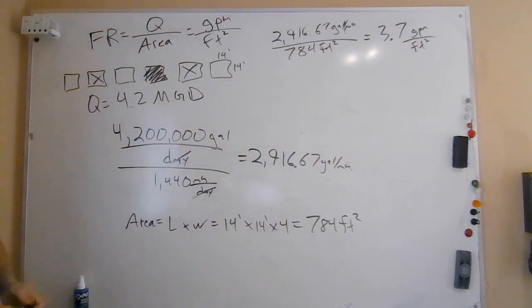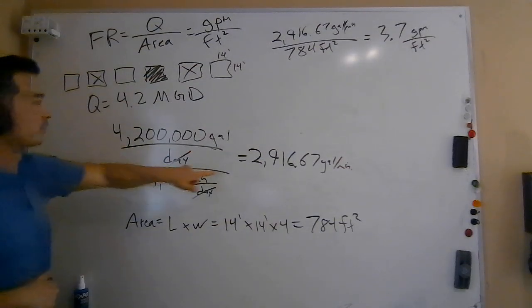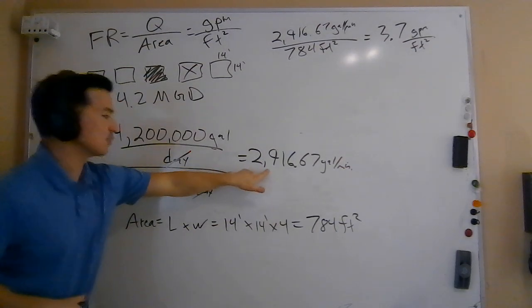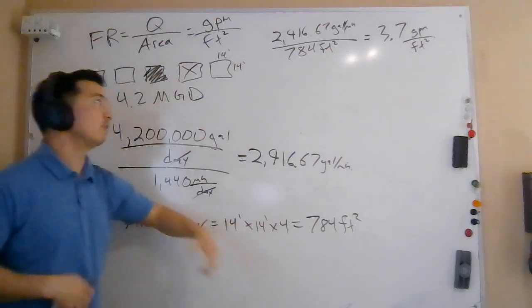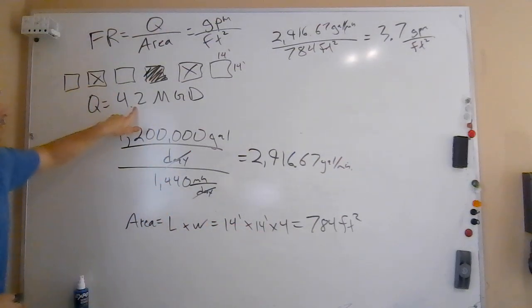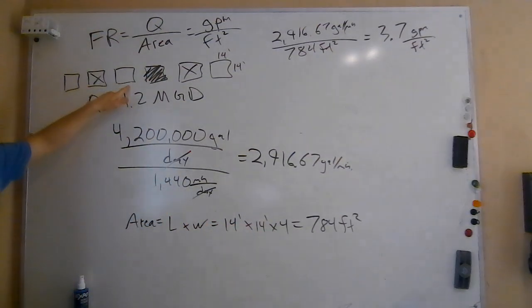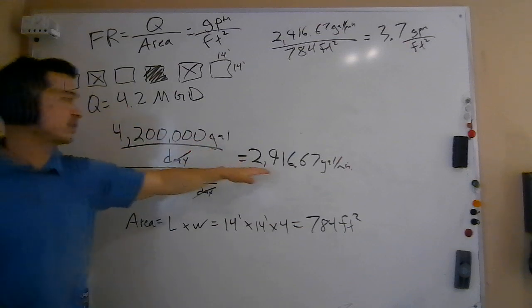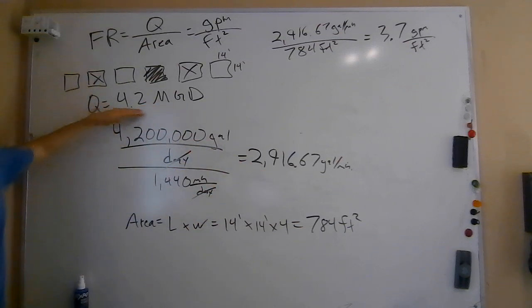The other way to think about doing this problem is instead of saying the total flow here is being treated by four filters, we could just say a quarter of the flow is being treated by one filter. So what we could have done in the beginning right here is said 4.2 MGD. We could have divided this by four. We could have divided this flow by four. Either way, we're accounting for a factor of four. So if we divide this by four, and we're going to get just over one MGD, that one MGD is what's being treated by one filter.